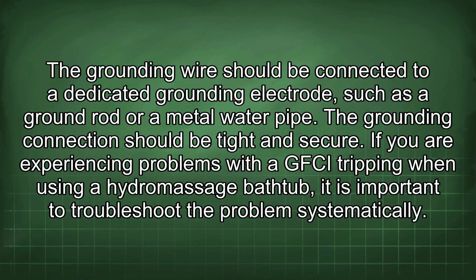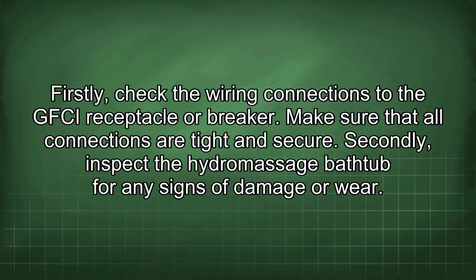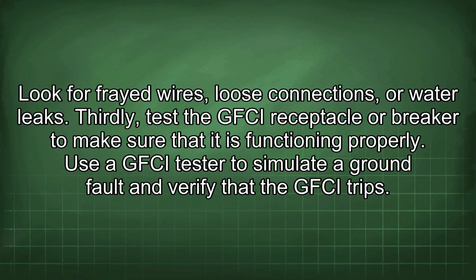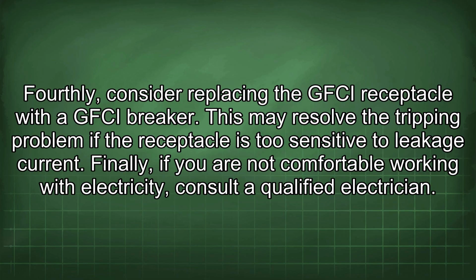If you are experiencing problems with a GFCI tripping when using a hydromassage bathtub, it is important to troubleshoot the problem systematically. Firstly, check the wiring connections to the GFCI receptacle or breaker. Make sure that all connections are tight and secure. Secondly, inspect the hydromassage bathtub for any signs of damage or wear. Look for frayed wires, loose connections, or water leaks. Thirdly, test the GFCI receptacle or breaker to make sure that it is functioning properly. Use a GFCI tester to simulate a ground fault and verify that the GFCI trips. Fourthly, consider replacing the GFCI receptacle with a GFCI breaker. This may resolve the tripping problem if the receptacle is too sensitive to leakage current.